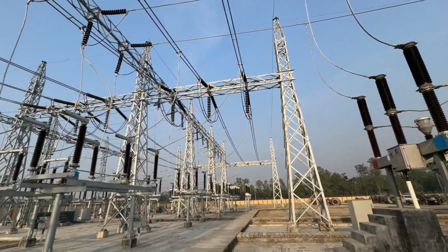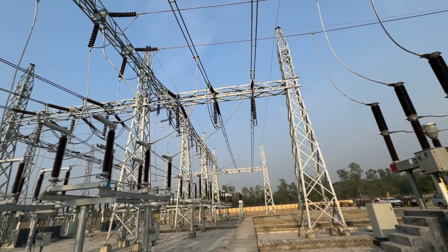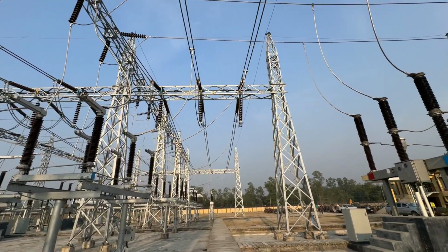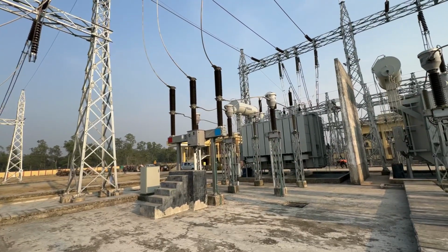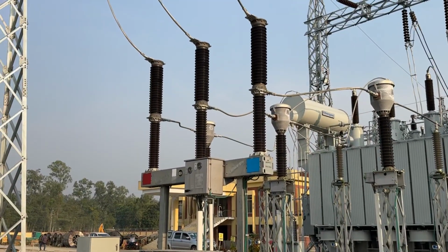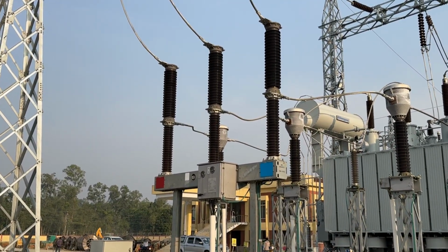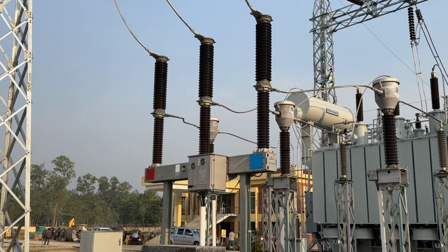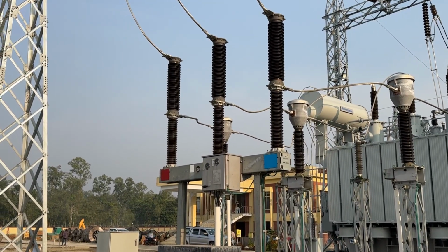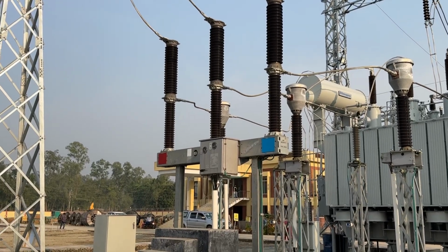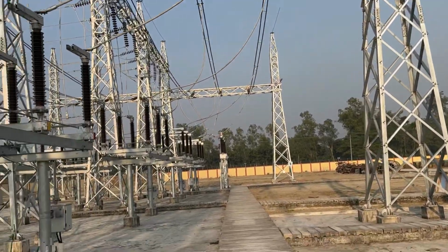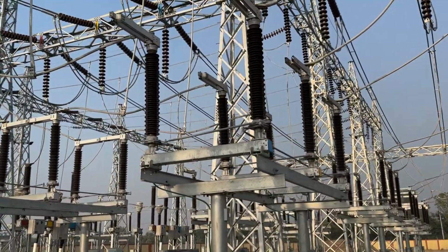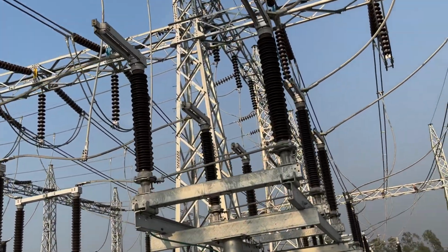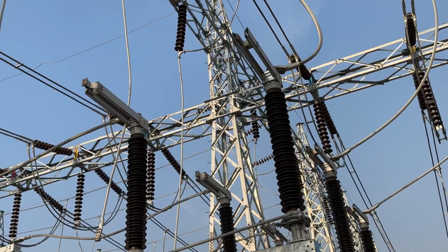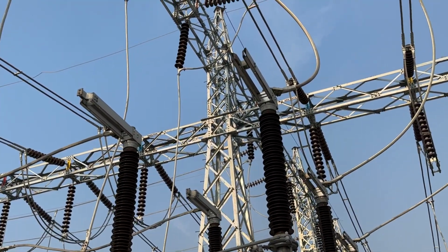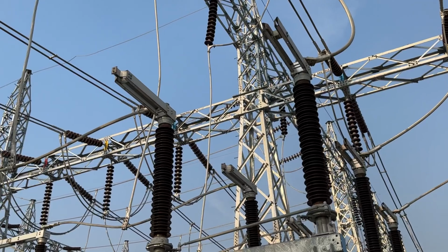This is on the 132 kV bus. It is mentioned here that the circuit breaker can operate in both load and no-load, any condition, no problem. Faulty condition as well as healthy condition. This one is an isolator. It is also a switching device, but an isolator can only operate at no load condition.